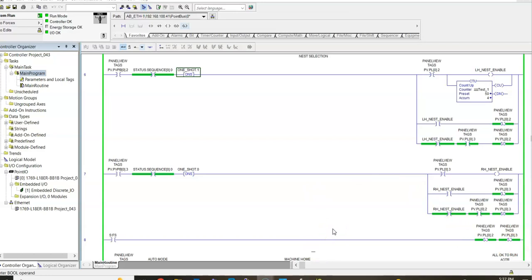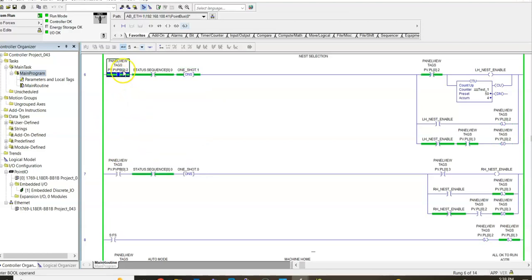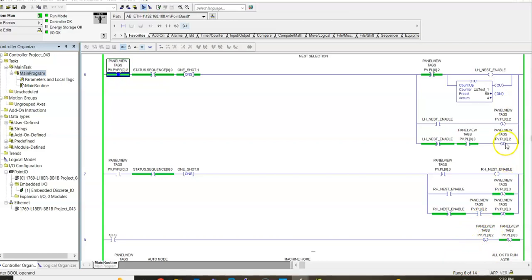Once that's done, what's going to happen is that will enable both nests to be eligible for production. First scan says you are starting this machine with the ability to use both nests. Now, to disable one of the nests, you would come up here and hit this button found on the panel view, right here on our panel view. Now what we've done is we no longer have our latch bit high here, panel view 0.2. That's been unlatched.